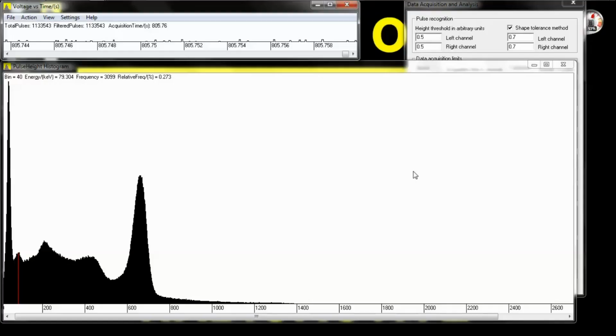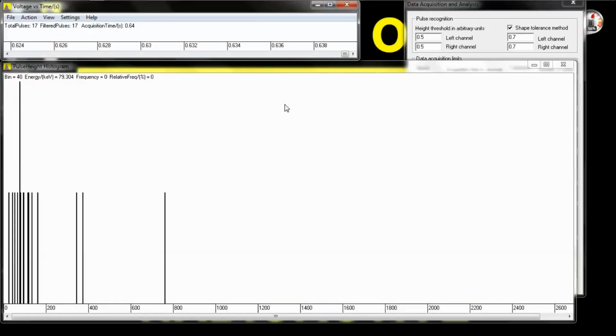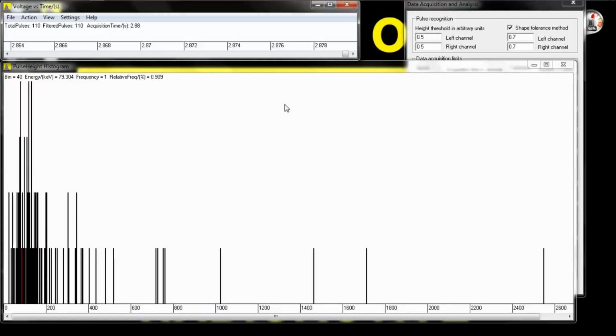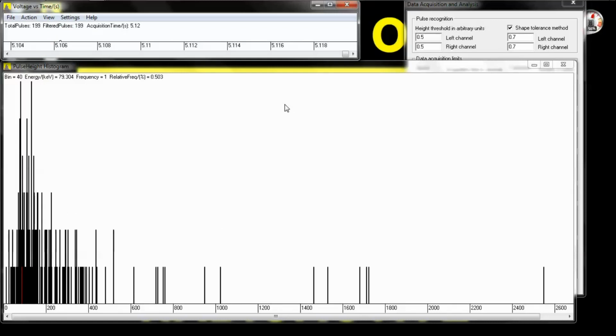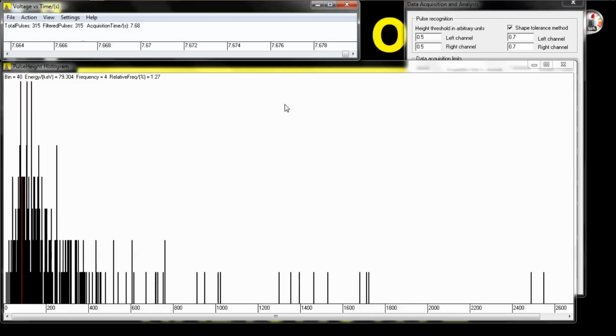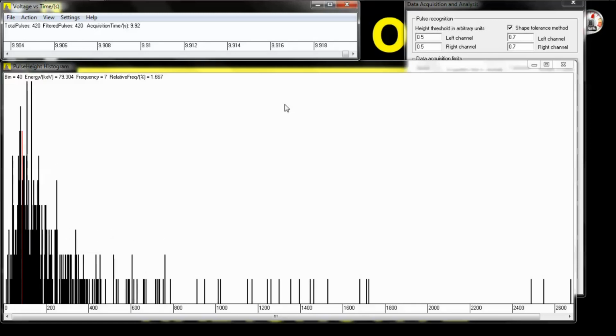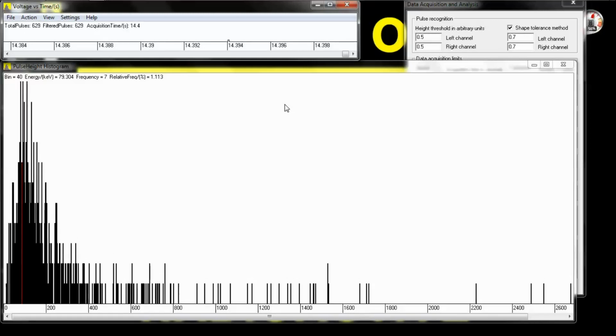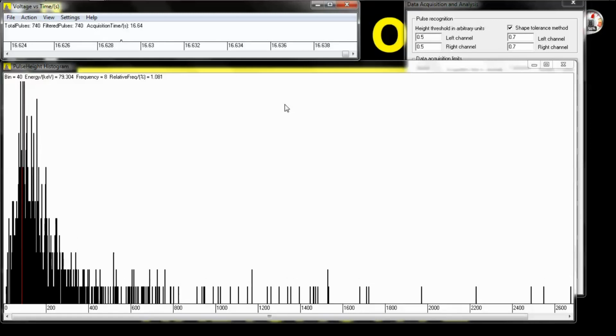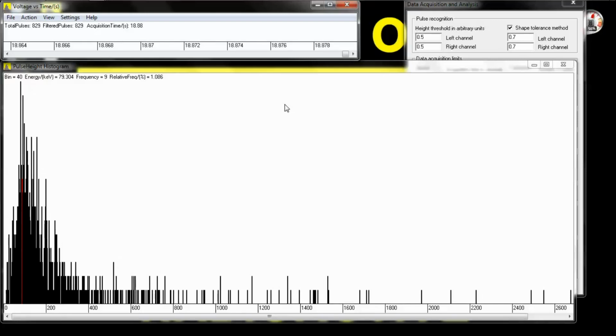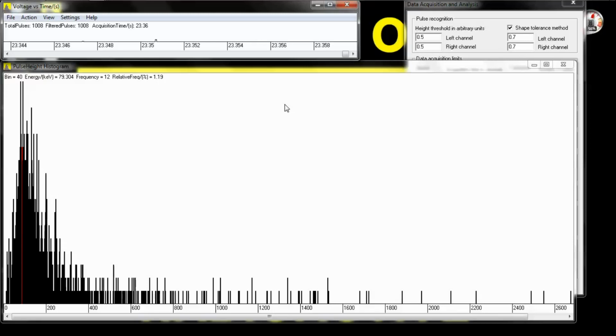Okay, with the sample now placed in front of the detector, we're ready to go again. Action, start accumulation. Now this doesn't have a big strong piece of cesium-137 in it, so it's likely that it will take a while for a spectrum to form. Now I'm going to speed this up for you, so what would be probably 10 minutes of spectrum accumulation is going to speed up to maybe a few seconds. So right now you see it at real time. This is what it looks like in real time. I'm going to speed it up now, and I'll be back in about 10 minutes time for you to see what the result looks like.